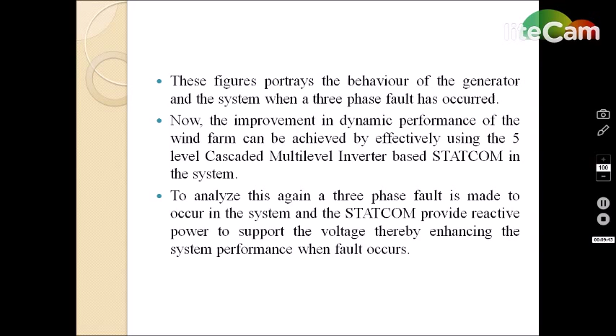So this performance can be improved by using a 5-level cascaded multi-level inverter based STATCOM in your system. To analyze this, again we have induced a three-phase fault, the same setup is made, and we just connected the STATCOM at the point of common coupling and measured. Now let's see the performance of PMSG with STATCOM.